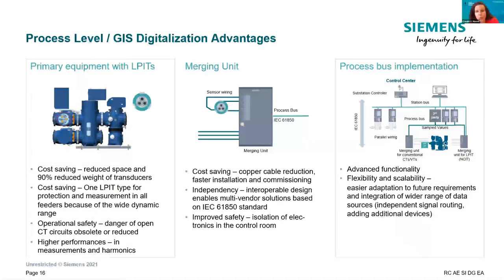So what exactly is the advantage of the LPIT, the merging unit, and the process bus implementation? Besides the weight and size that help save costs, especially where land is expensive, there's also operational safety. In a place like Oman, where you have a lot of space, operational safety is the best argument, along with the higher performance you get with the LPIT, because you get a reduction in the danger of open short CT circuits.